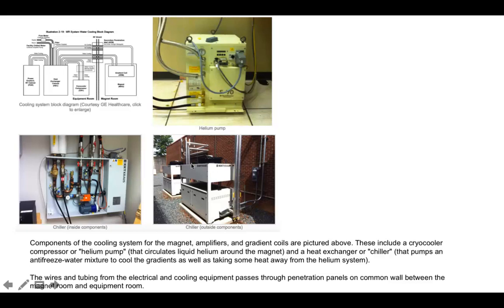here's the external part of the system that deals with your main electrical and cooling equipment exterior, and usually the helium storage tanks are placed either inside these cabinets or in another special cabinet. So often the helium supplier can come and replenish your helium without disrupting anything, should it need to be replaced or replenished on a regular basis. They can just come in and they don't have to take the system offline or anything. There are interconnects built in.